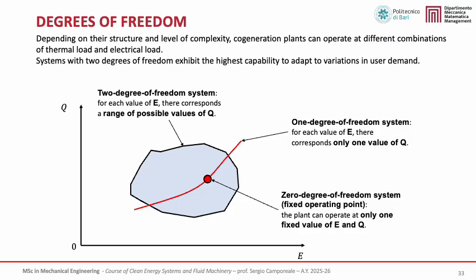In this slide, we build on the energy plane representation to introduce the concept of degrees of freedom in CHP systems. Depending on their structure and level of complexity, cogeneration plants can operate at different combinations of electrical and thermal load, which translates into different regions of the QE plane. A system with 0 degrees of freedom operates at a single fixed point. Both electrical and thermal outputs are fixed and cannot be adjusted. In a system with 1 degree of freedom, for each value of electrical output E, there corresponds only one value of thermal output Q. This indicates a strong coupling between electricity and heat, typical of many conventional CHP units.